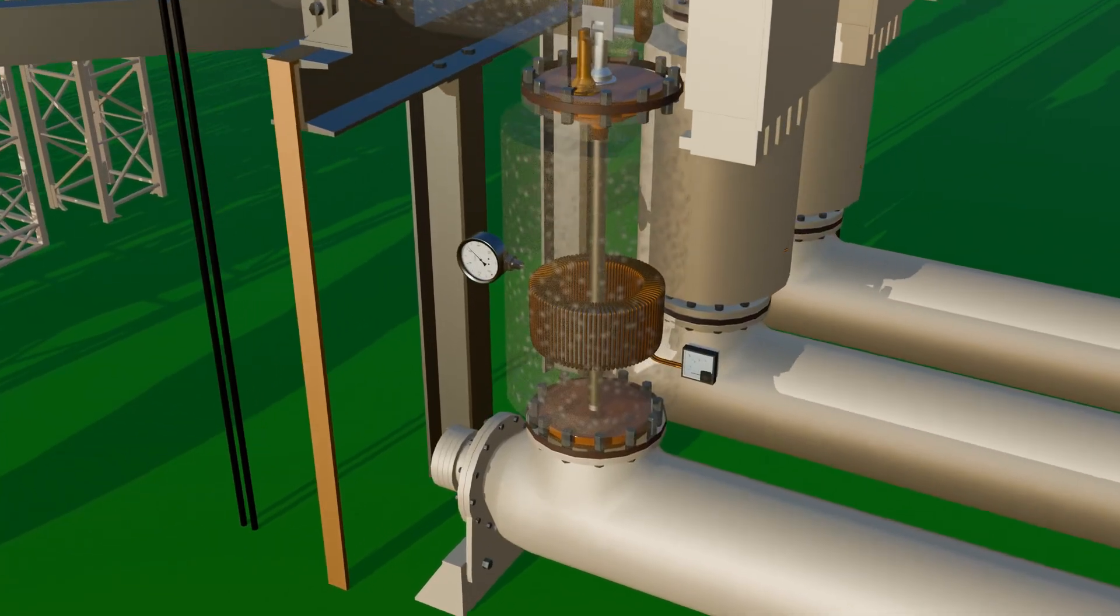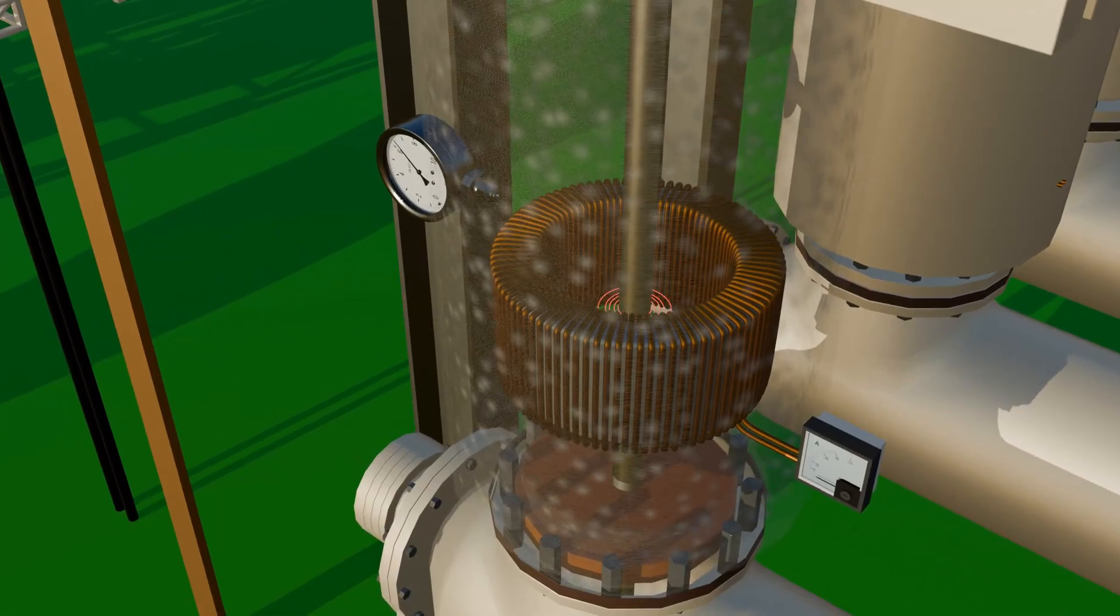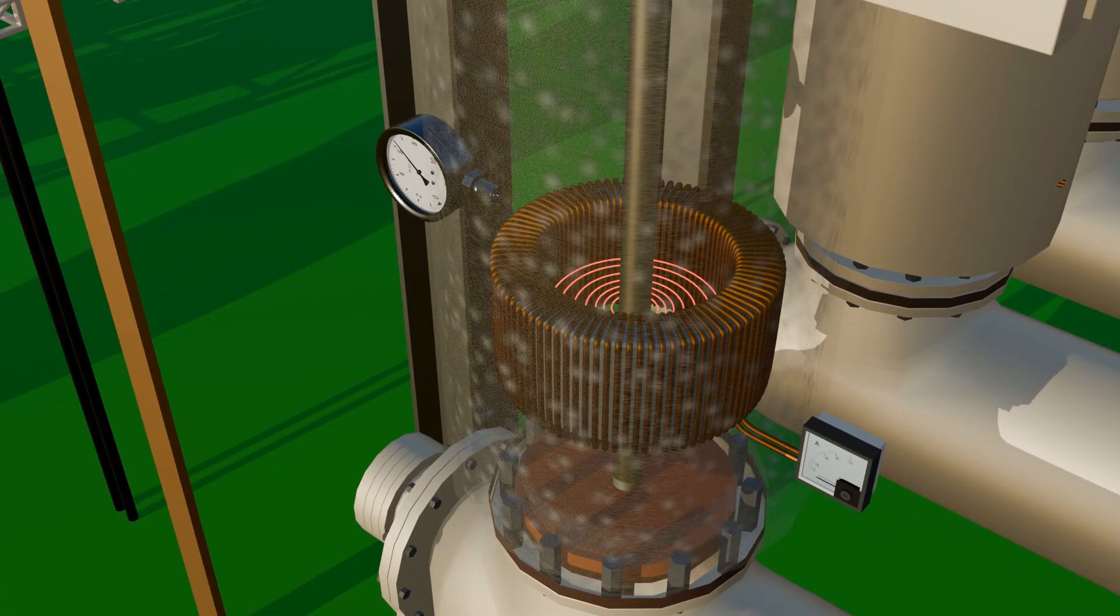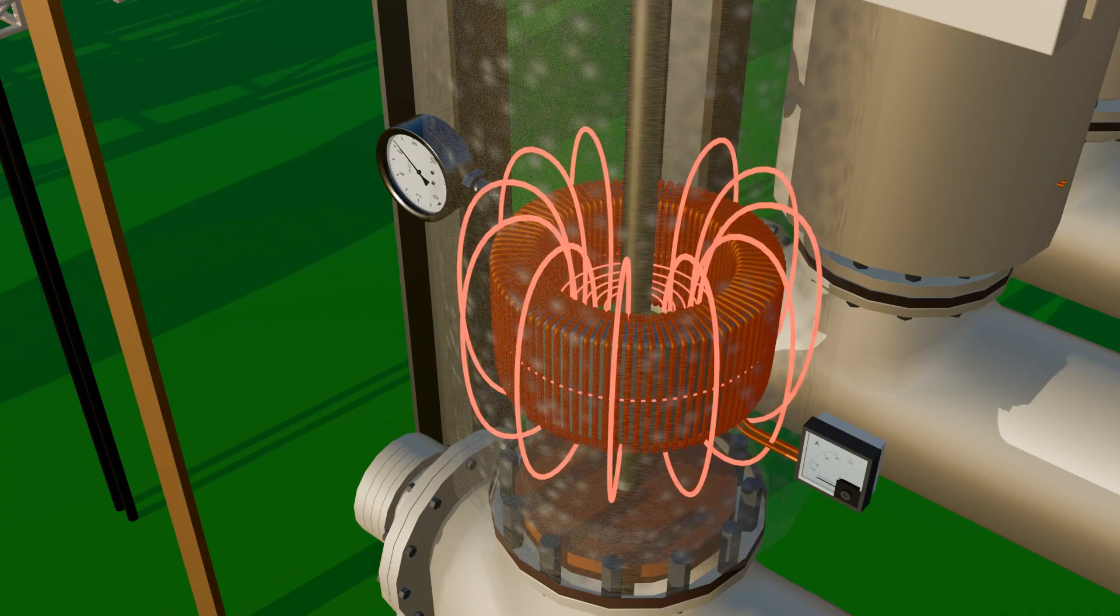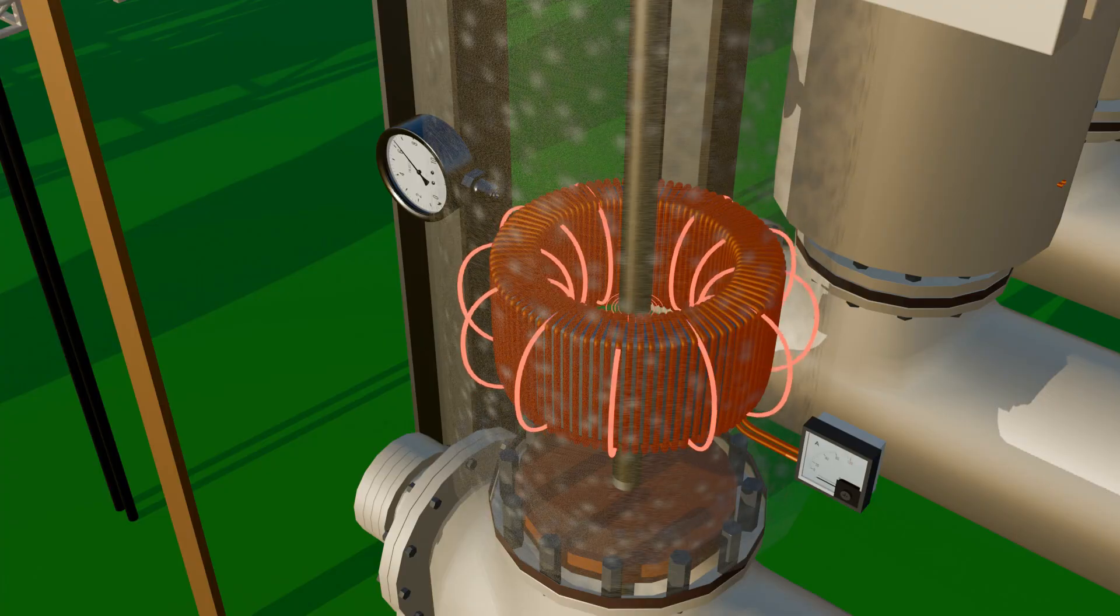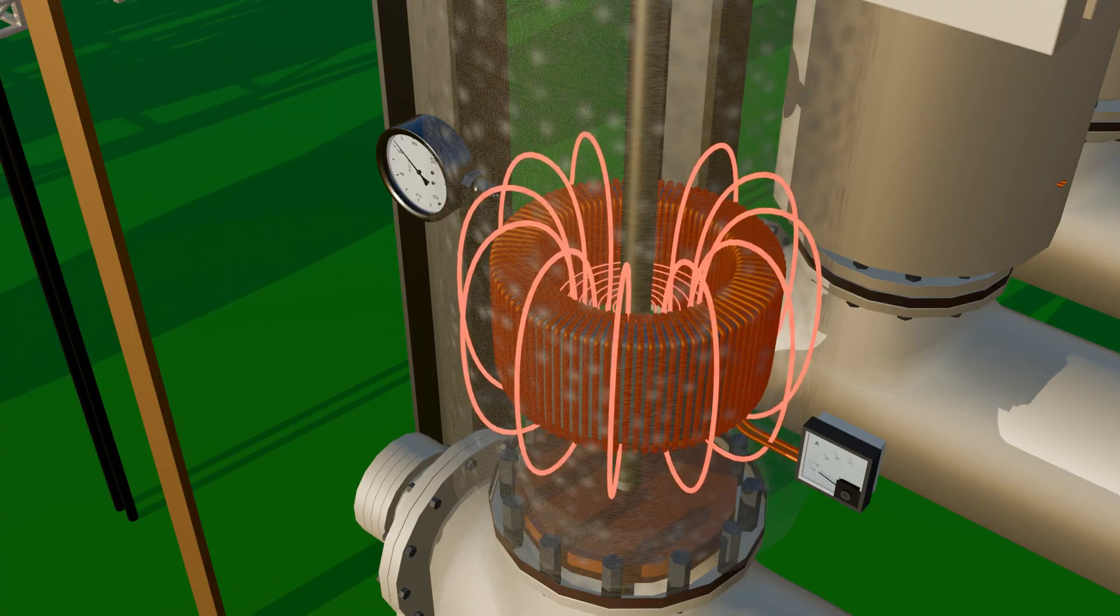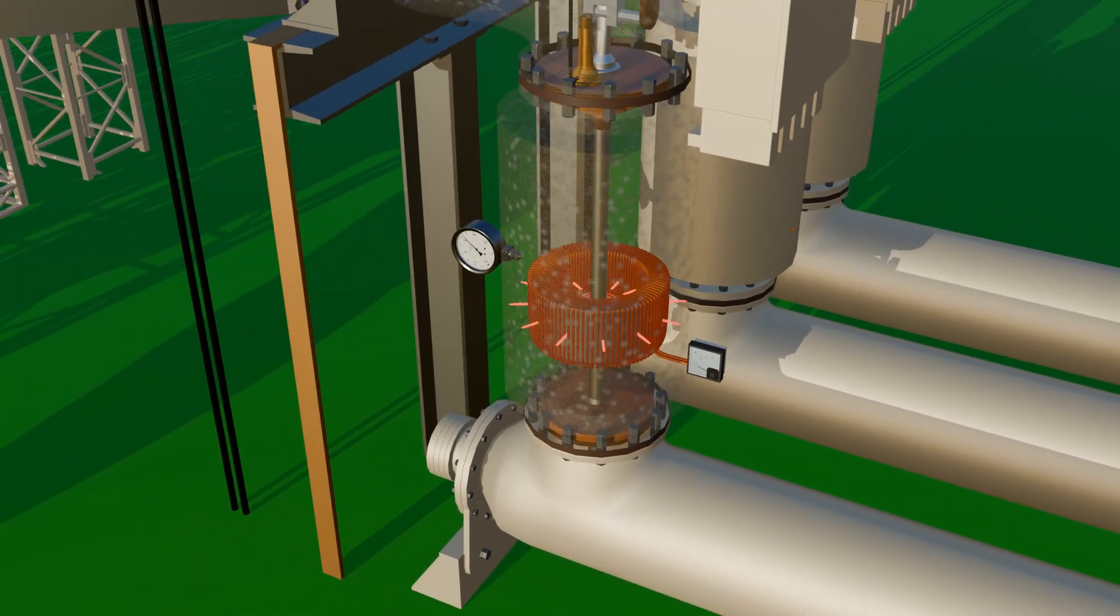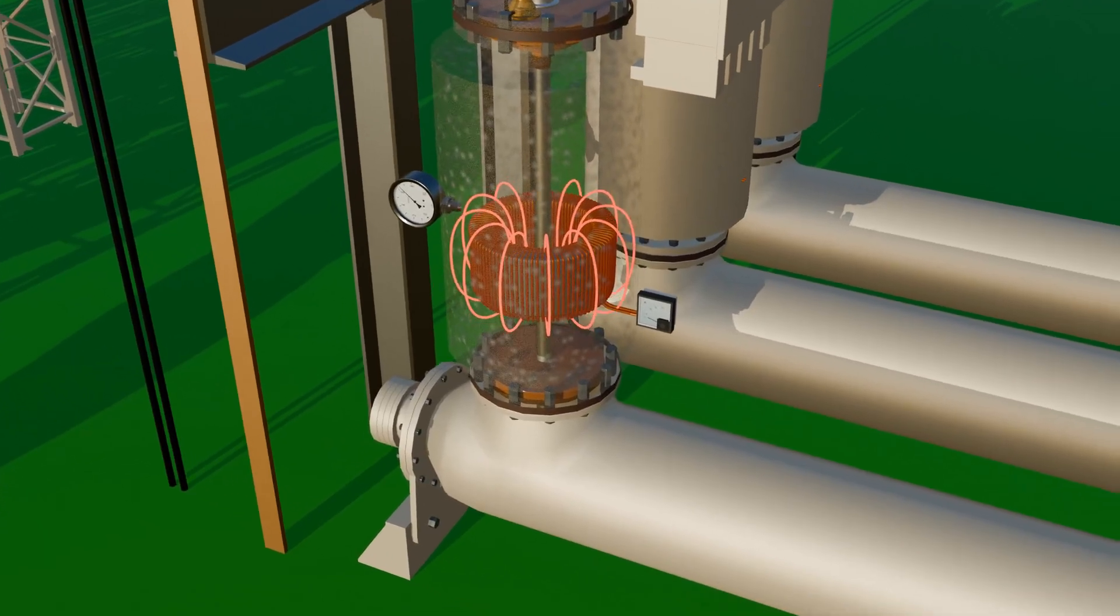After the isolator comes the CT block, the current transformer, which is used to measure current. In a CT, the main conductor itself acts as the primary winding, and around it a toroidal secondary winding is placed containing a very large number of turns. Because of this high turns ratio, the output is reduced to about 5 amperes, which can then be measured safely with standard meters. The current transformer also measures fault current. When a fault occurs, the current rises sharply. The CT detects this rise and sends a signal to the circuit breaker.